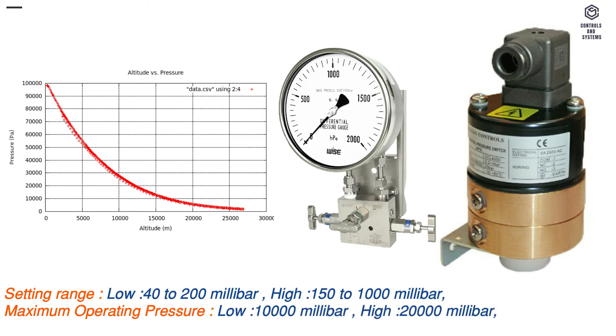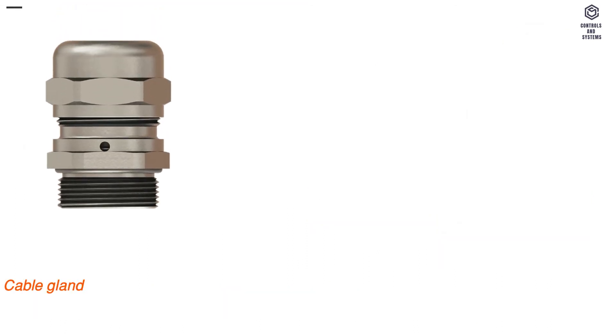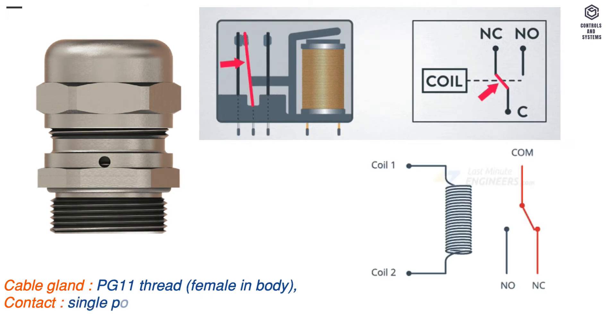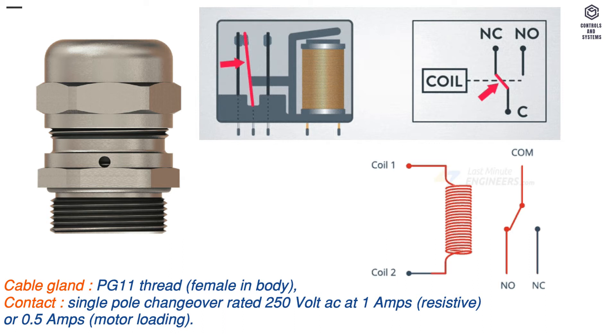Cable gland: PG-11 thread, female in body. Contact: single pole changeover rated 250 volt AC at 1 amp resistive, or 0.5 amps motor loading.